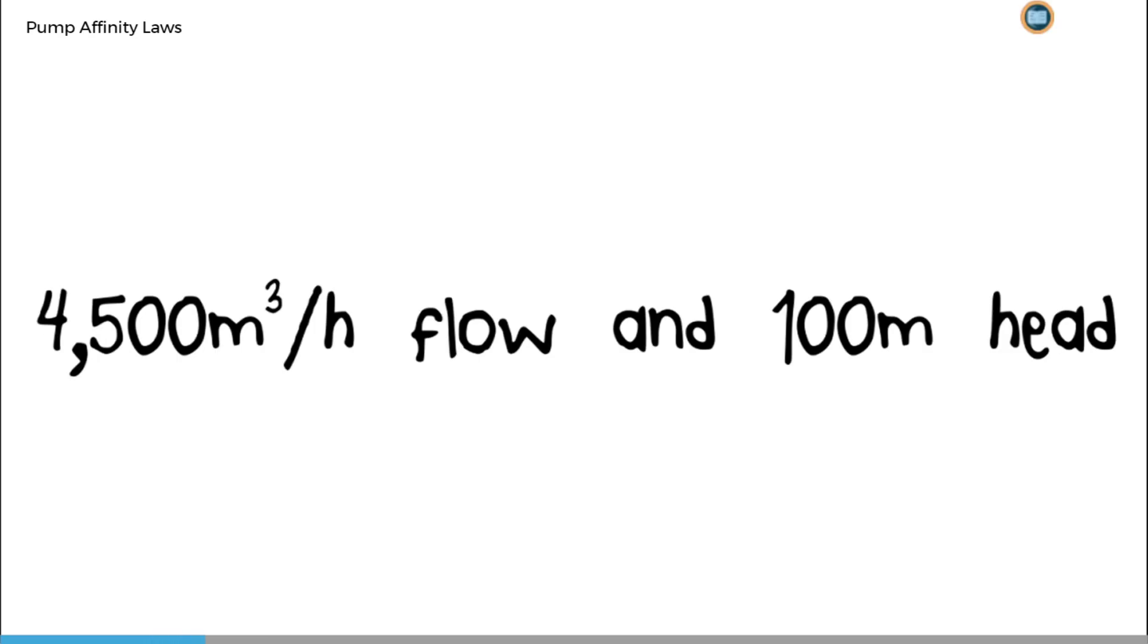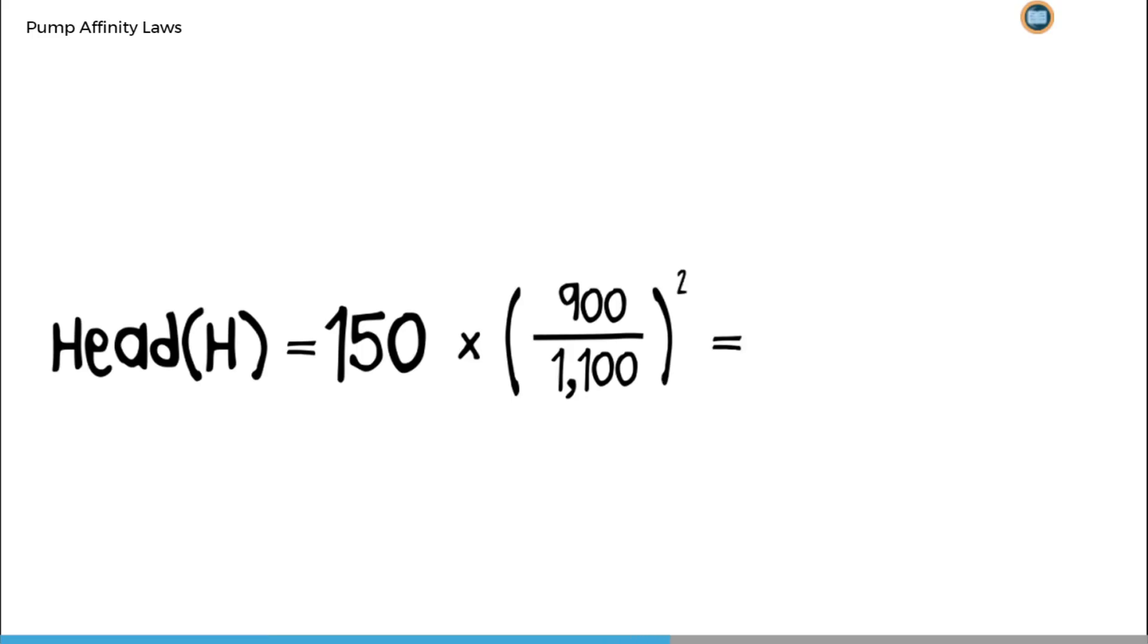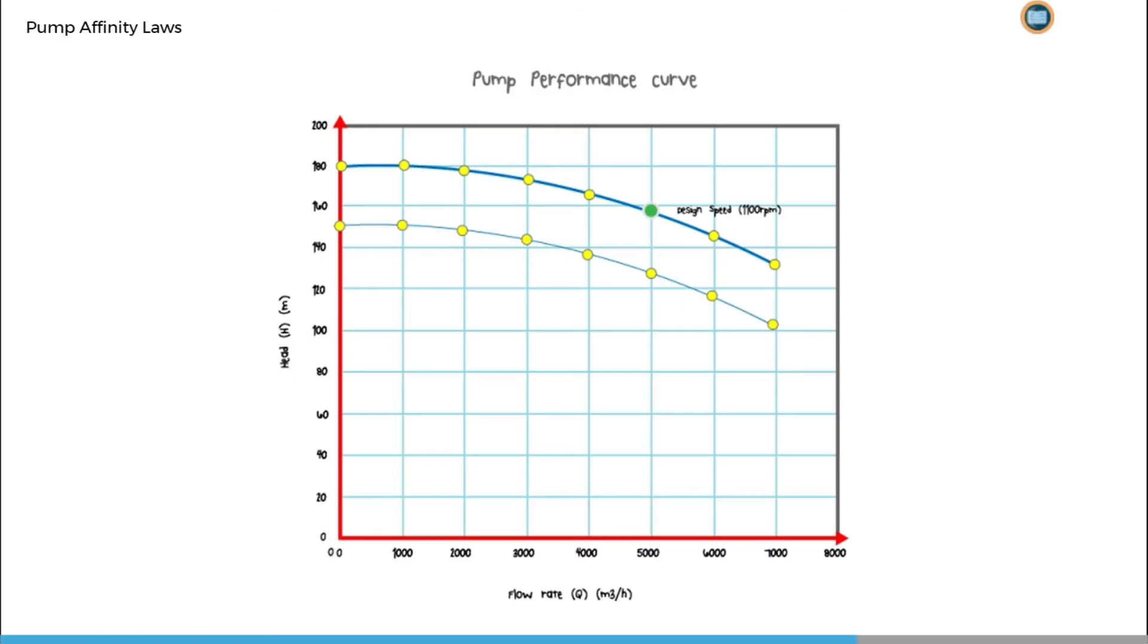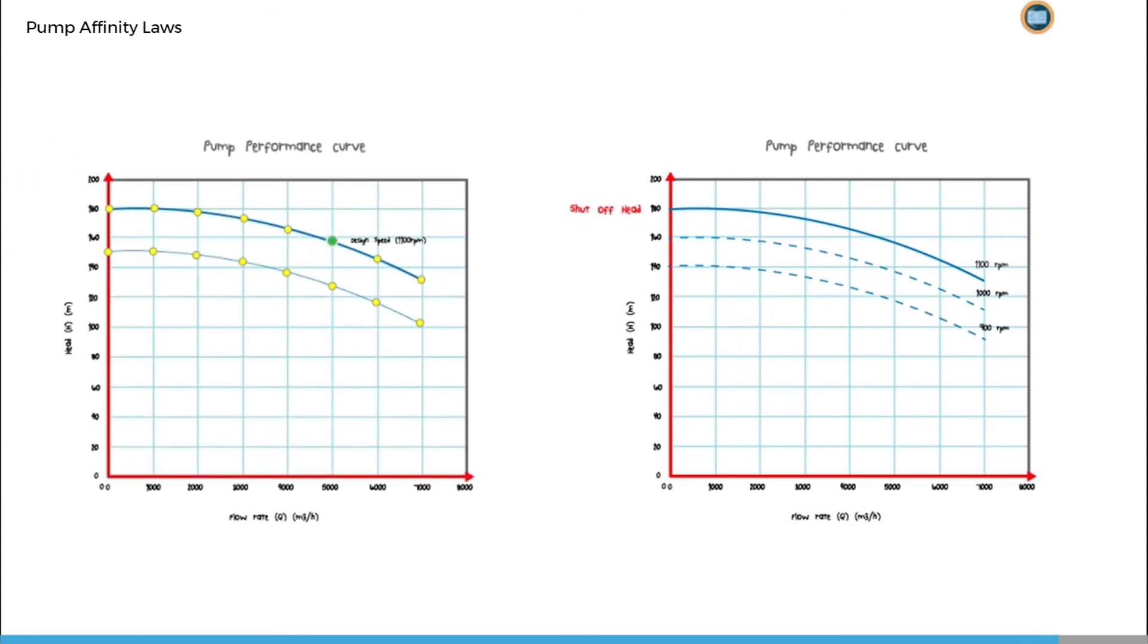Using our formula from earlier, we can work out the flow rate by multiplying the design flow rate by the pump rotational speed divided by the design rotational speed. This gives us a flow rate of 4,500 metres cubed per hour. Similarly, we can work out the head by multiplying the design head by the pump rotational speed divided by the design rotational speed all squared. This gives us a head of 100.4 metres. In fact, we can calculate the head and corresponding flow rates for all points on our performance curve. We can do this for a range of pump speeds. The resulting performance curves will be mathematically similar to the design performance curve or HQ curve for design speed that we saw earlier in the module.